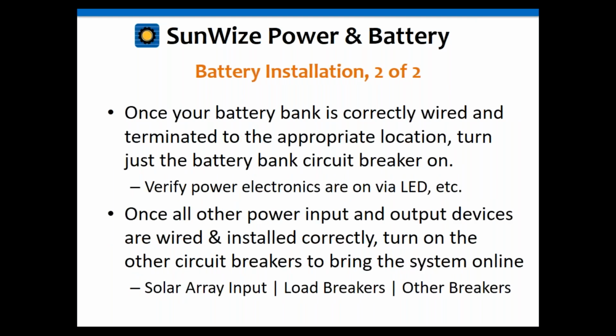Once your battery has been correctly wired, and we're going to get into the series parallel wiring a little bit later, and terminated at the right location, you're going to want to turn the battery circuit breaker on first. The battery circuit breaker should always be the first circuit breaker turned on and the last one turned off, because it's kind of the balance for the whole system. It's the reference voltage that the whole system is using. So it's very important that that is the first thing turned on and the last thing turned off.